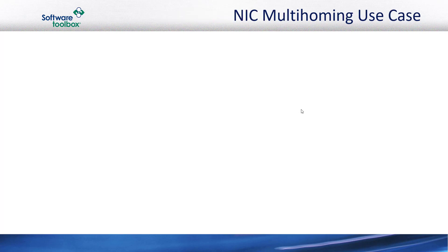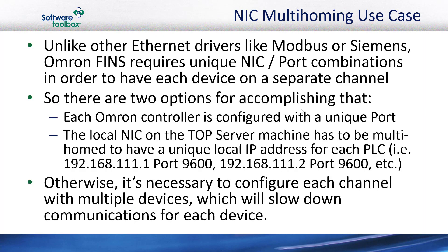Last but not least with best practices, we also have what we refer to as NIC multi-homing, and there are some use cases for that. Unlike other Ethernet drivers in TopServer like Modbus or Siemens, the Omron FINS protocol requires a unique network adapter and port combination in order to have each device on a separate channel. One of our general best practices for TopServer is that each device should have its own channel if it's an Ethernet driver for the best communication, so TopServer can communicate with all of your Ethernet PLCs in parallel without having to do round-robin polling. With Omron FINS, it's different because it requires that unique NIC and port combination.